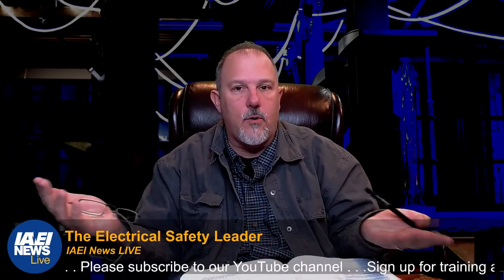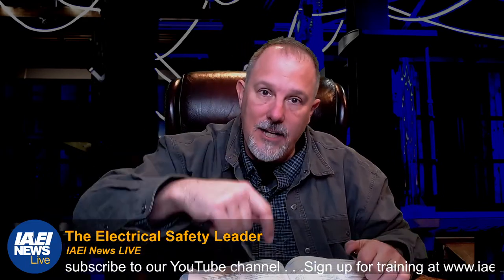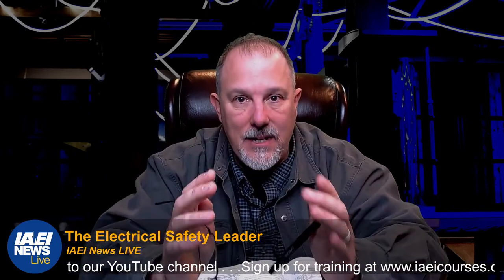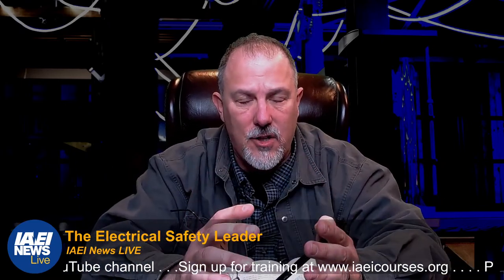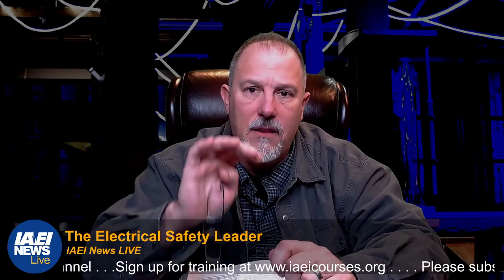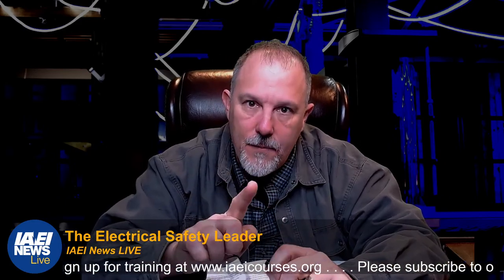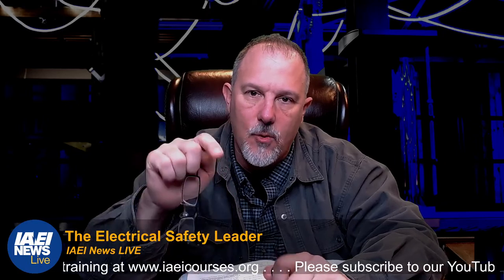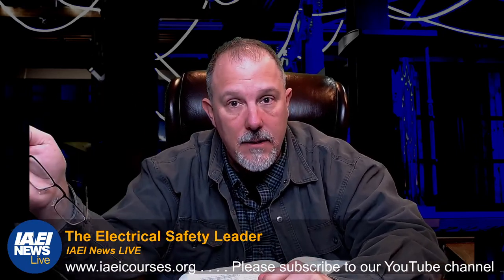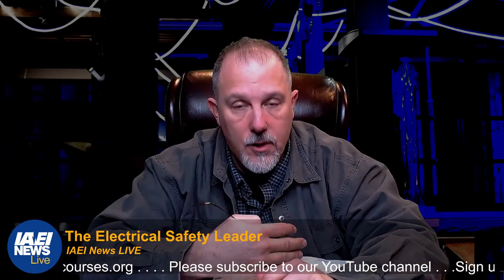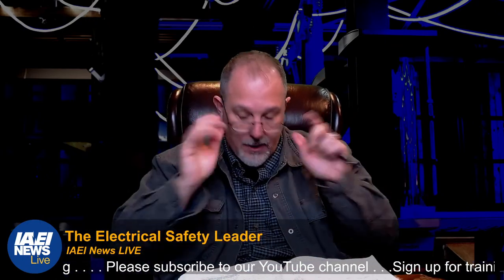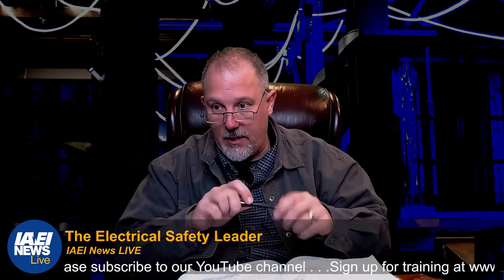You know there's no arc flash hazard because it's low voltage given where you're at in the system, but you know your primary hazard is shock. You know how to do the boundaries, generally know the product, but you've never actually landed wire. What do you know about torque? What do you know about the installation requirements, the space inside the box, how many conductors you can put in there? That's a little different than what we talk about when we discuss a qualified person with regard to worker safety. So I think there's an opportunity. I don't know what I don't know, I'm just saying I think there's an opportunity.